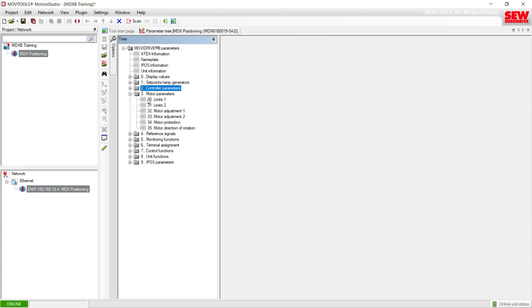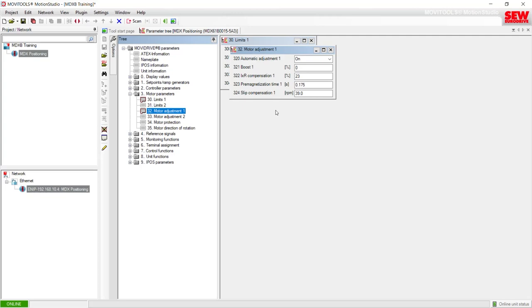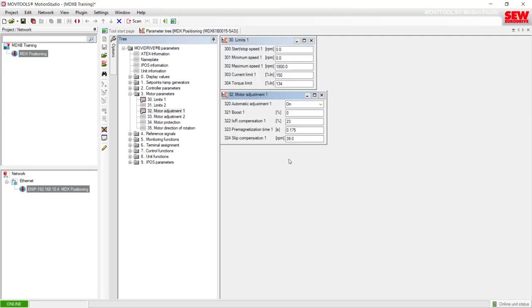Folder 3 is Motor Parameters, where you'll find most of your motor limits and some tuning parameters. Limits 1 is for parameter set 1 and includes start and stop speeds, minimum and maximum speeds, and current and torque limits. Limits 2 would be for parameter set 2. For additional tuning adjustments there is item 32, Motor Adjustment 1, with additional tuning parameters for the motor.